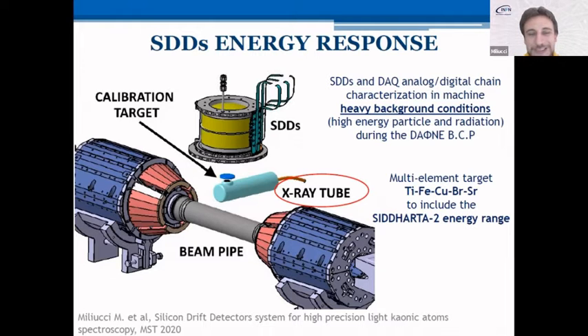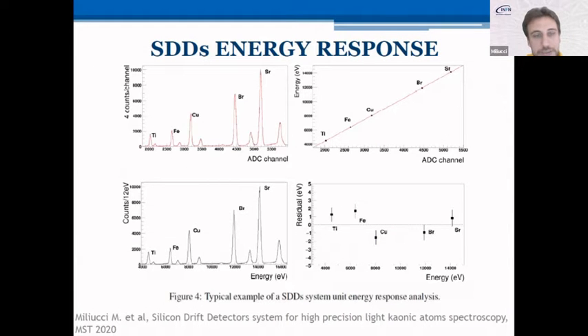Why? Because we know for sure that this is the worst condition to test the energy response of the SDDs. So we did it like this. We put an X-ray tube below the target cell, of course outside the vacuum chamber, with a multi-elemental target made of titanium, iron, copper, bromine, and strontium. In such a way, we cover the whole energy range of the SDDs. And we did a study of the energy response in this heavy background condition, made of high energy particle radiation, also directly hitting the SDDs. These are the results. Here you clearly see the 10 peaks, the K alpha and K beta of the five elements. This is an example of a single unit.